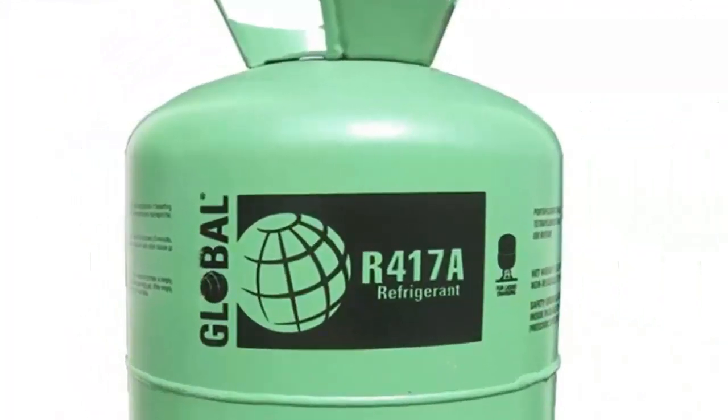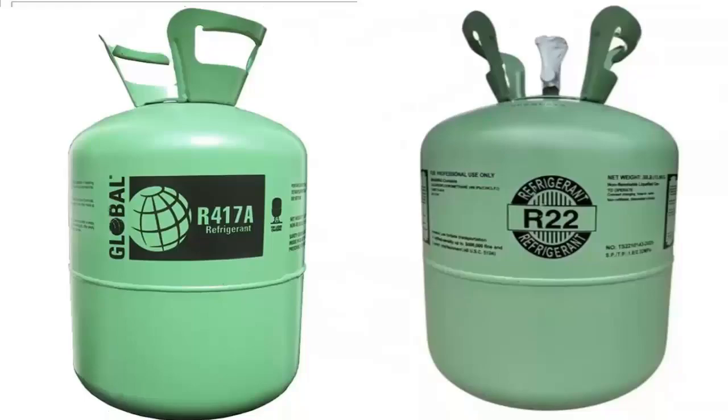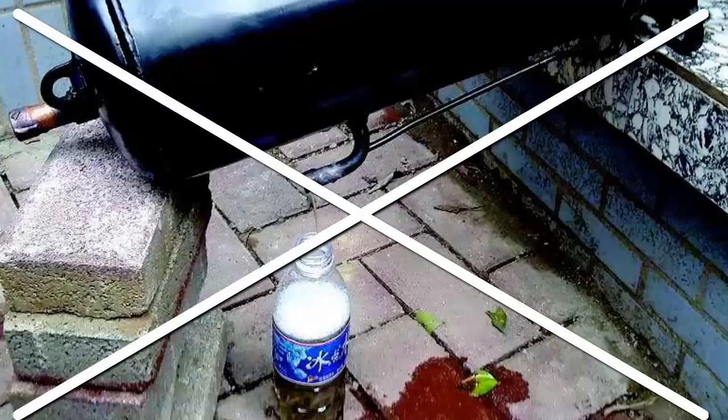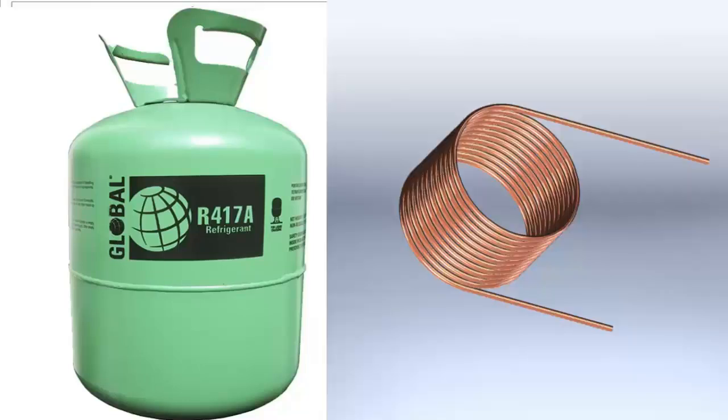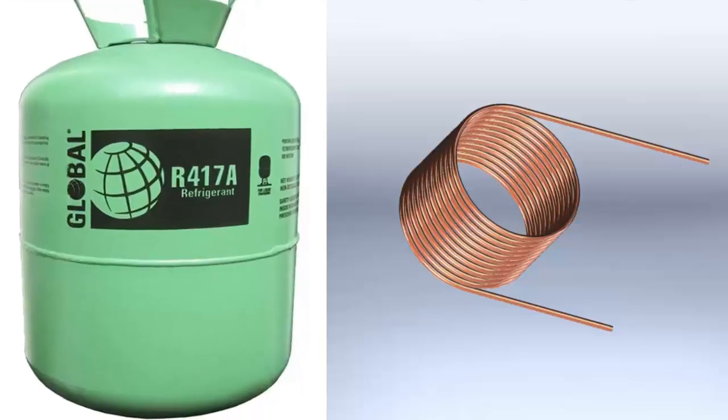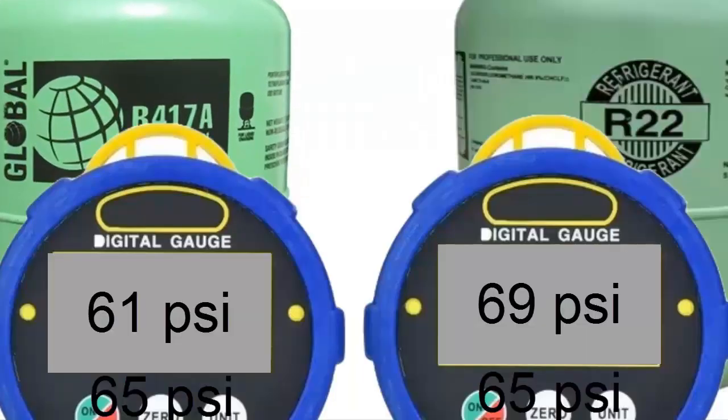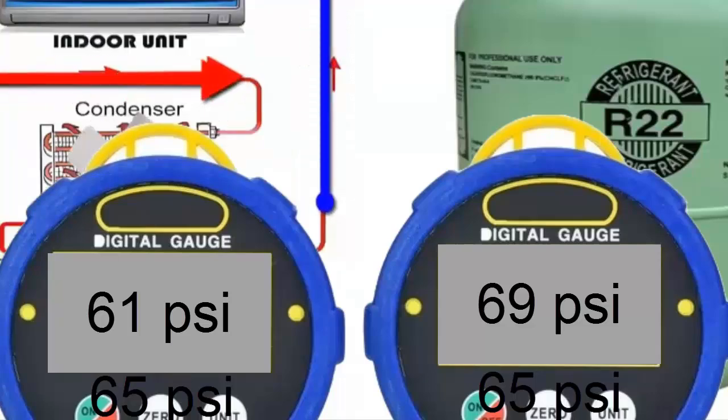D. R417a. This replacement gas for R22 does not require changing the compressor oil. The recharge must be done in the liquid phase, and the original R22 capillary tube should be used. On screen, we compare the working pressures of both refrigerant gases.